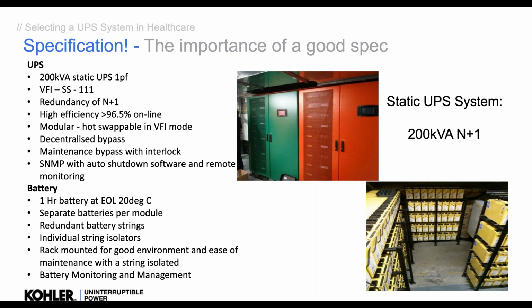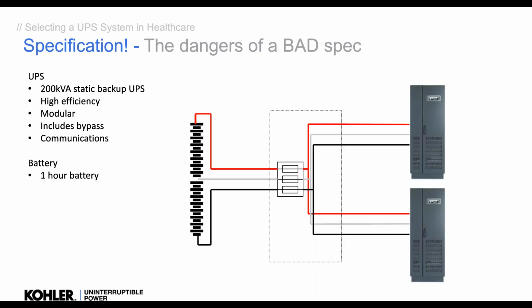Okay. Specifying the power factor, the quality, the redundancy, the efficiency, all these things is very critical with the battery. An hour battery at end of life at 20 degrees, separate batteries per module, redundant battery strings, all this stuff will get you a good system that you want. Okay, if you don't, you tend to get a bad system. It fulfills a poor spec in a poor way. Okay, so please, be very careful of what you're specifying and how you do it.